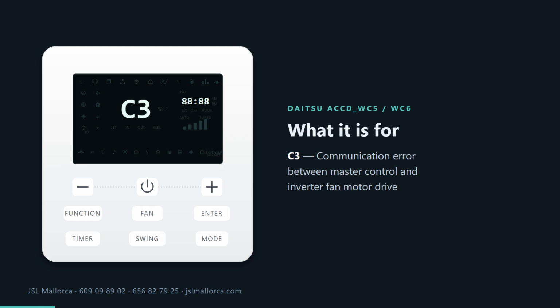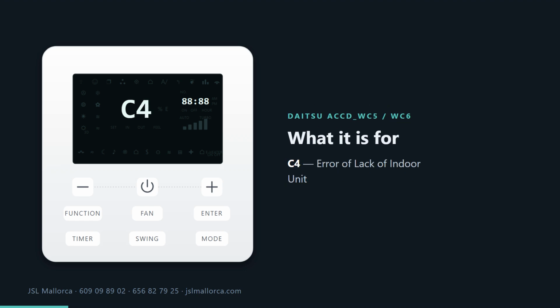Code C3. According to the manufacturer, communication error between master control and inverter fan motor drive. Code C4. According to the manufacturer, error of lack of indoor unit. Code C5. According to the manufacturer, alarm of indoor unit project number collision.